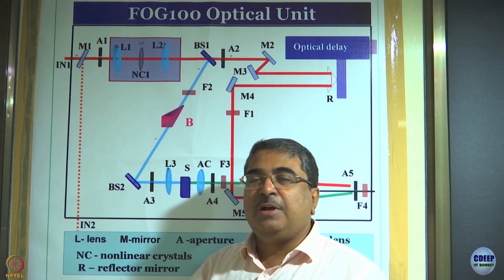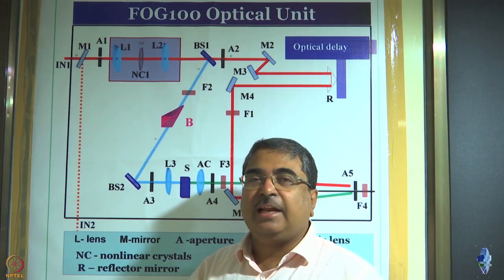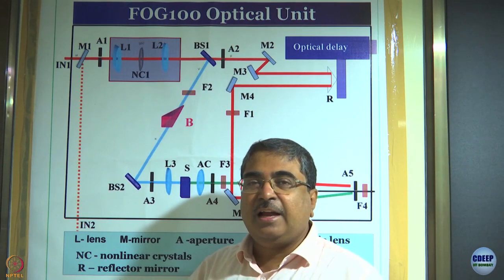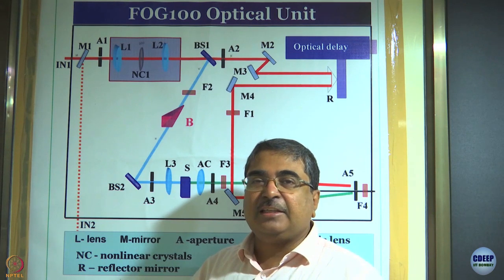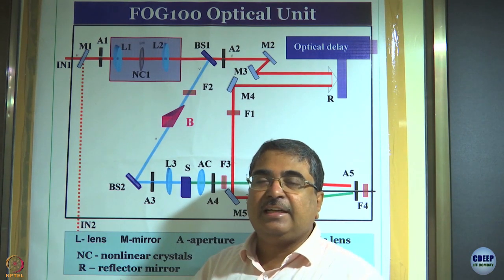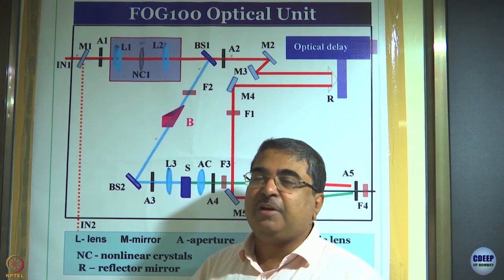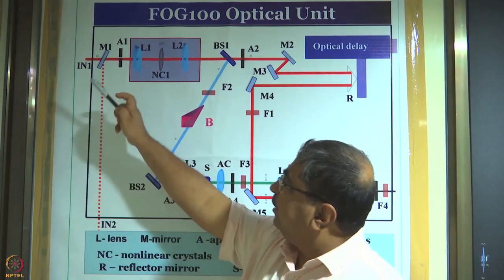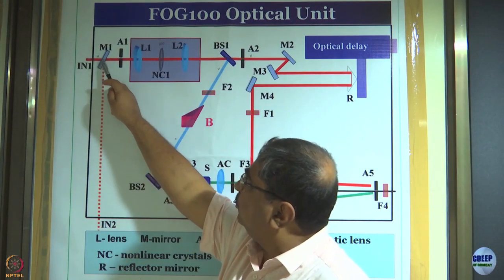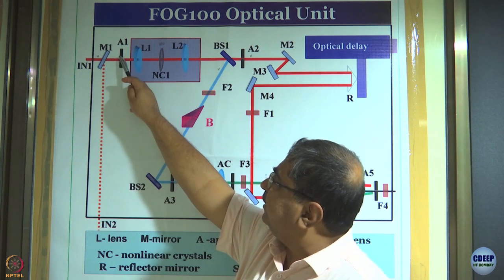In our case, the light is tunable from 690 nanometers all the way to 950 nanometers from a femtosecond pulsed titanium sapphire laser. Later on in this course, we are going to open up the laser used as a light source for this instrument. For today, we just take the laser as a light source: 100 femtosecond pulses, 80 megahertz repetition rate.